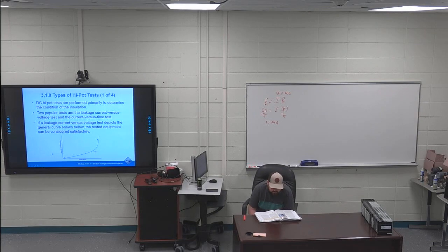My highlight for this splits the pages. So it starts on page 30 in the bottom right of page 30, right there where you see point C in parentheses, about 6 lines up through point D on page 31. At some point the current will start rising at a more rapid rate. That's called the knee, point C. This will show up on the plot as a knee in the curve.